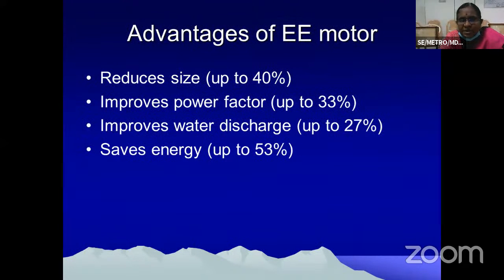So the advantages of an energy efficient motor are that it reduces the size up to 40% and improves the power factor. Nowadays you don't have a power factor incentive, you have only a power factor penalty. So you have to operate the power factor at 0.9 and above. So it improves the power factor, improves water discharge up to 27%, and saves energy up to 53%.